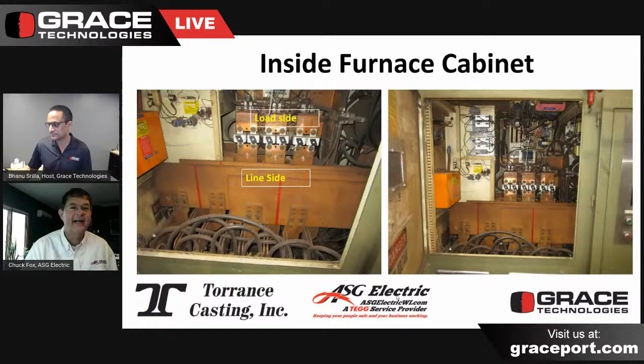So if we open up the door to the cabinet, this is what we see, and we see a lot of very large busing in the foreground of the cabinet, and all of that busing is still on the line side of the disconnect for the rest of the cabinet. In the middle, there are white assemblies that sit between line and load. Although it's hard to see in this picture, those are actually fuses that go across the busing from the line to the load side.